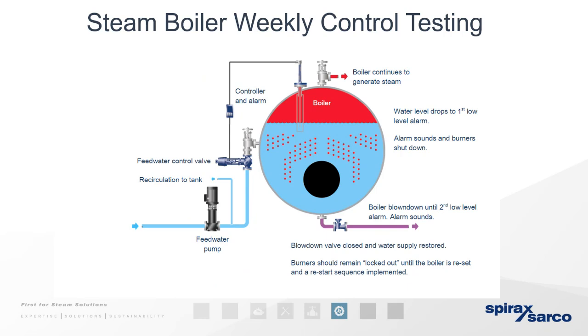The mass of water released during the weekly test is the volume between the normal water level and the second alarm. That's the total volume you're getting rid of, and this is what the BDV capacity is sized on. So the blowdown vessel should be sized from the normal running level of your boiler all the way down to the second low level alarm. That total volume is the capacity for the blowdown vessel. Hopefully that makes sense.